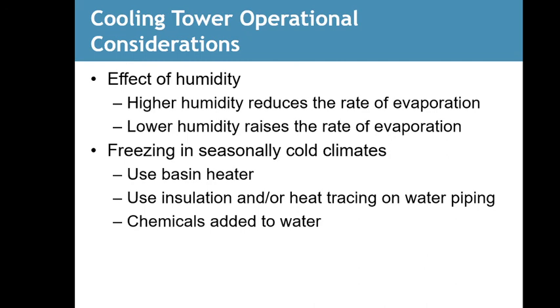Freezing in seasonal cold climates: use a basin heater, and we're talking about the water basin. Use insulation or heat tracing on water piping. This is going to be something that will have some sort of heat going to it, and it could be just insulation, or it could be wrapped by a wire that stays warm to keep the water from freezing. Chemicals can also be added to the water, like an antifreeze.